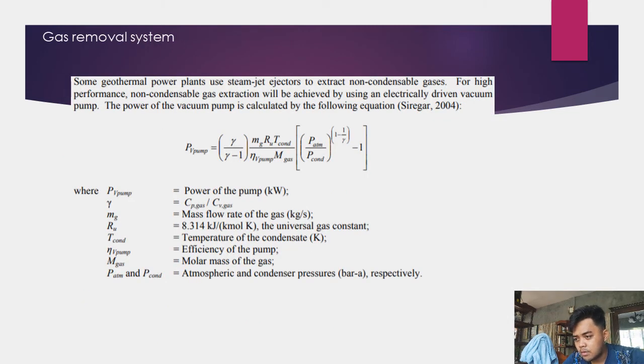Some geothermal power plants use steam jet ejectors to extract non-condensable gas. For high performance, non-condensable gas extraction will be achieved by using an electrically driven vacuum pump. The power of the vacuum pump is calculated by the power equation, where P sub V pump is equal to the power of the pump in kilowatts.